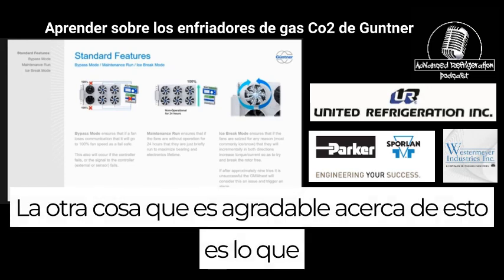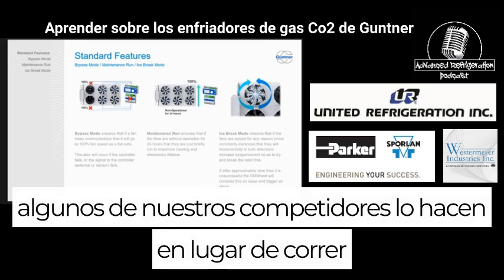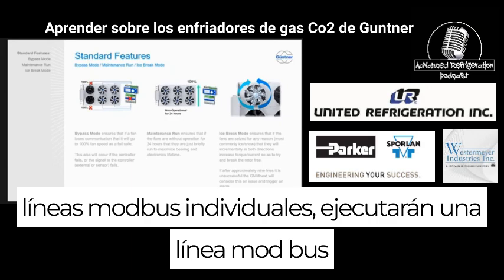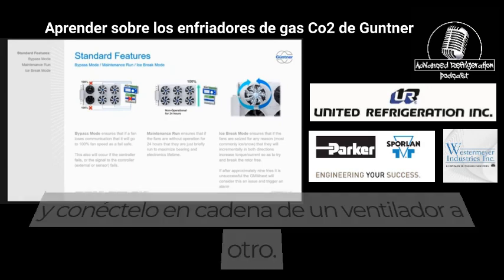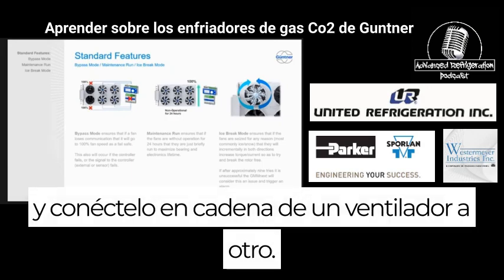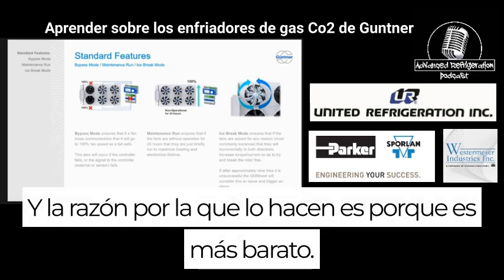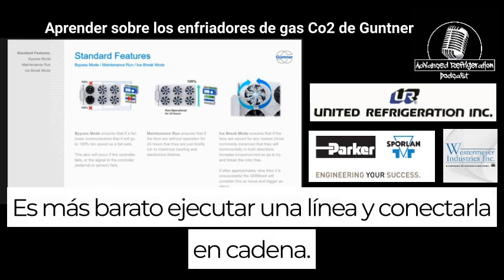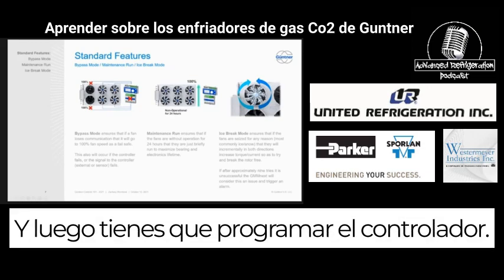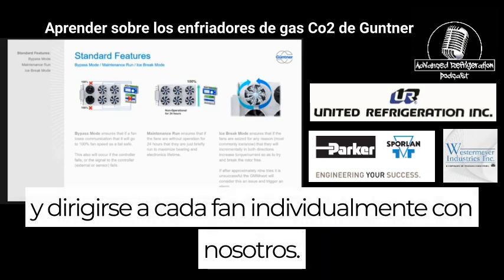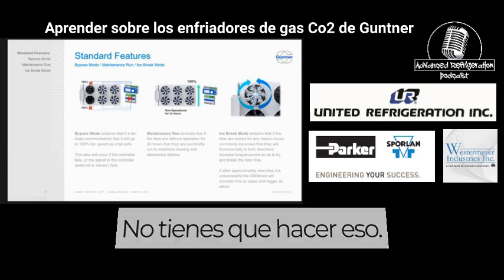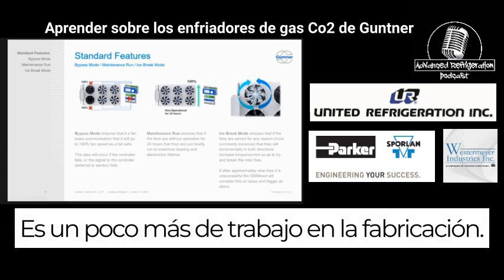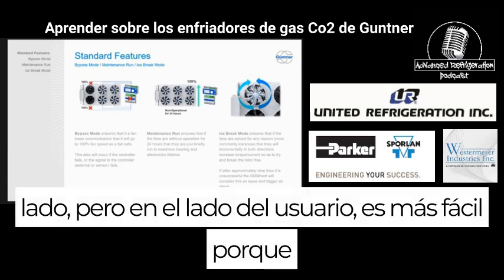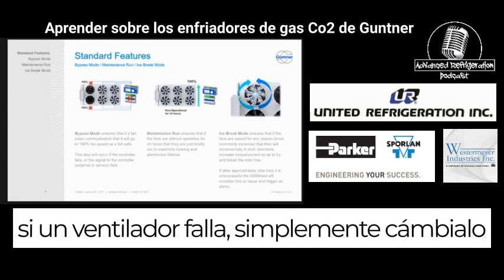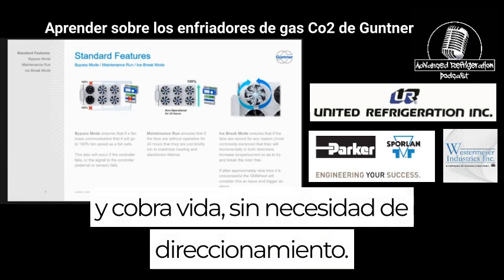The other thing that's nice about this is what some of our competitors do. Instead of running individual Modbus lines, they'll run one Modbus line and daisy chain it from fan to fan. And the reason they do that is because it's cheaper. It's cheaper to run one line and daisy chain it. And then you have to program the controller and address each fan individually. With us, you don't have to do that. It's a little bit more work on the manufacturing side, but on the user end, it's easier because if a fan fails, you just swap it out and it comes alive.